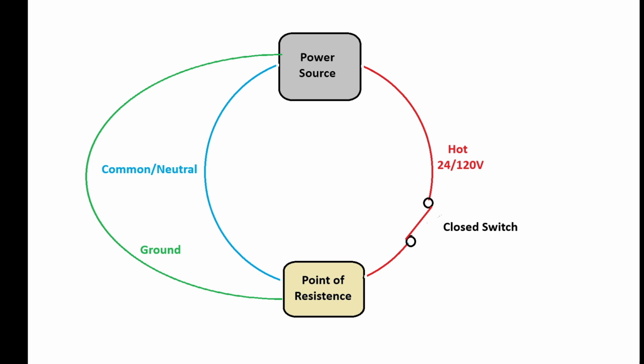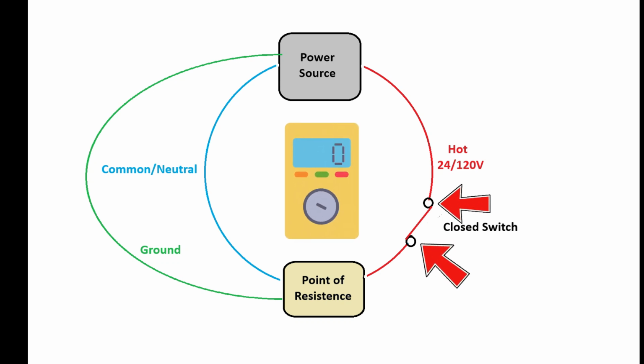Let's go back to the closed switch. If I were to put my probe on the hot side of that switch, and then I place my probe on the other side of that switch, and let's say I'm reading 0 volts. What I'm dealing with here is a problem of not knowing whether I'm reading 0 volts because I have a power problem that's not delivering voltage to begin with, or if I'm reading 0 volts because I have no potential across a closed switch in a powered circuit. So what I have to do is move my reference points around in order to verify my readings so I'm not being fooled by these things.